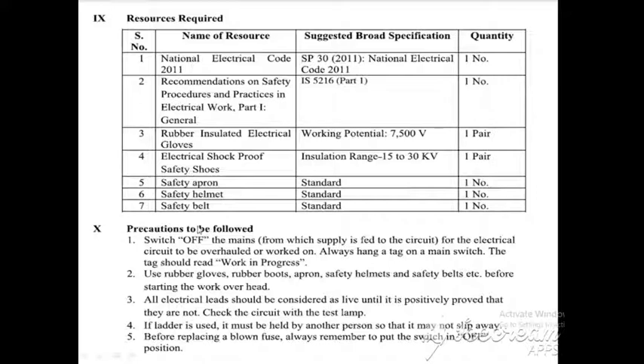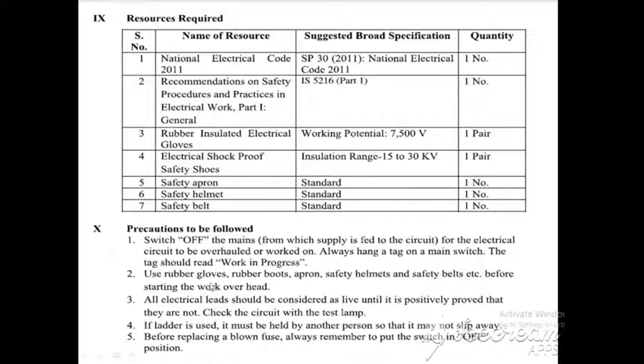Next are precautions to be followed. While working in electrical installation, precaution number one: switch off the main supply or main switch from which supply is fed to the circuit to be overhauled or worked on. Always hang a tag on the main switch — the tag should read 'work in progress.' Also use rubber boots, apron, safety helmet, and safety belt before starting our electrical work, meaning we wear the safety accessories before beginning work.